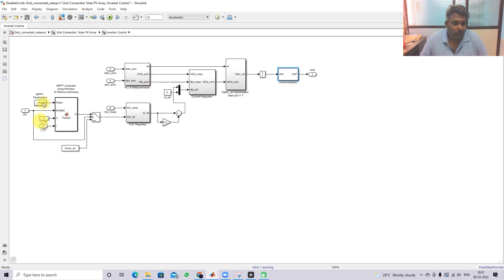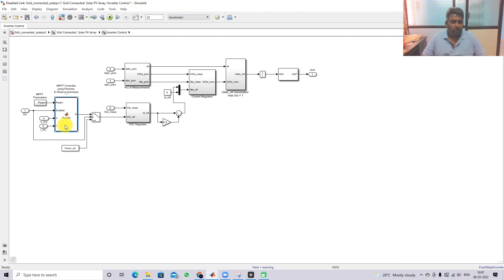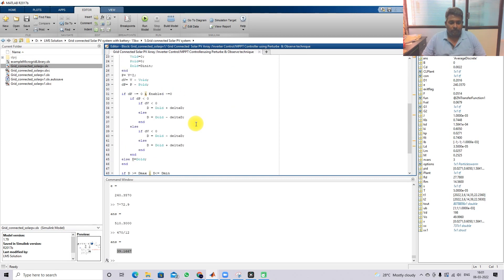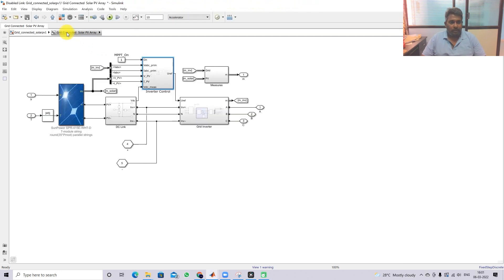The inverter control uses P&O MPPT to extract maximum power from the PV panel. It receives two inputs: PV voltage and current. Inside the P&O MPPT block, we find the change in power and change in voltage, and based on those we adjust the reference voltage. The P&O MPPT provides a reference voltage which is then compared with the actual DC link voltage.